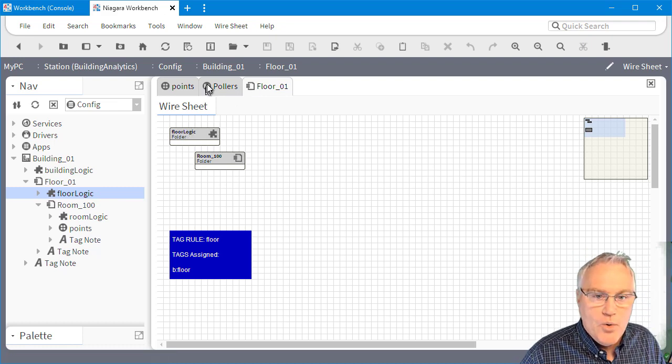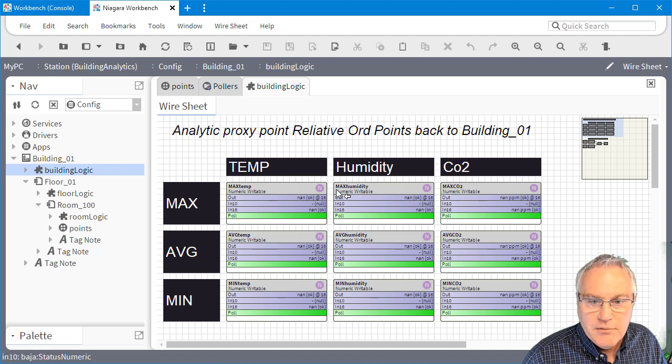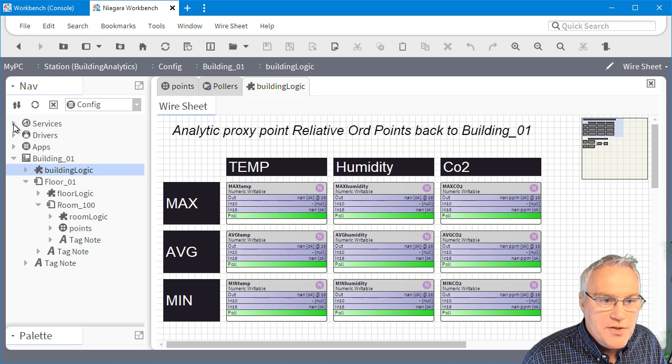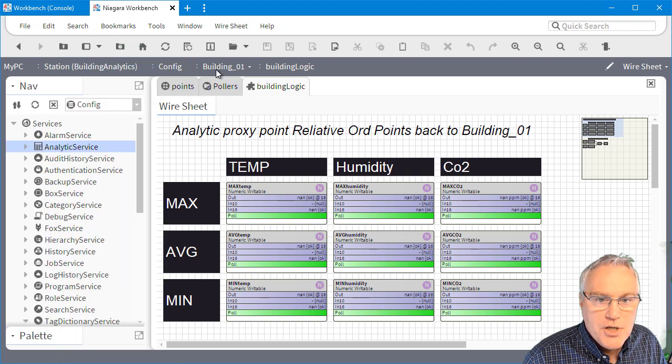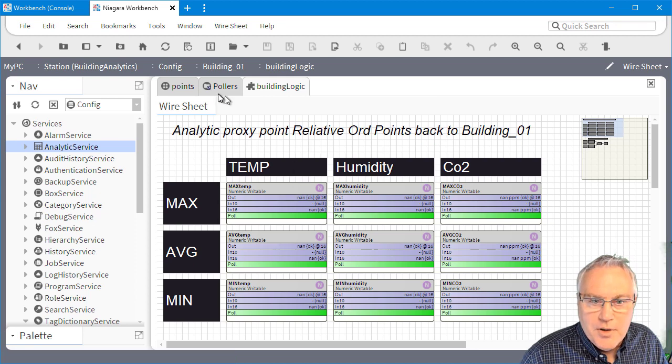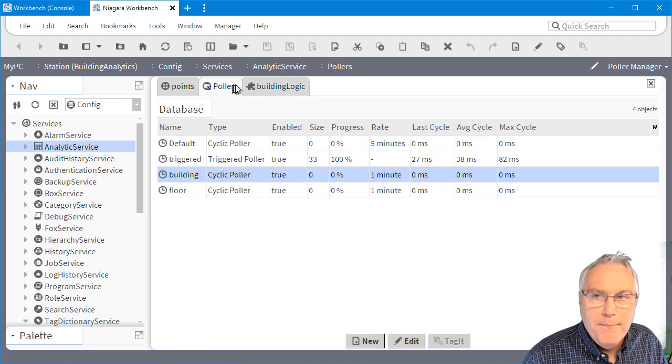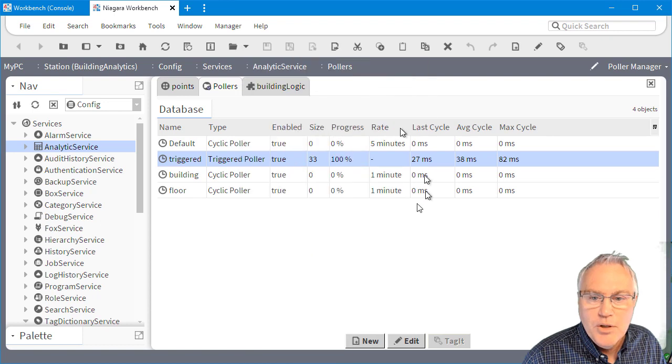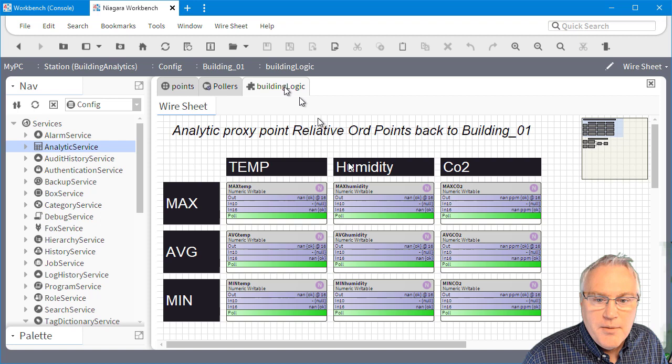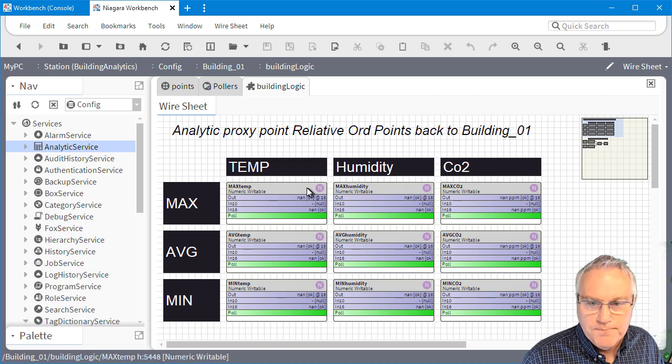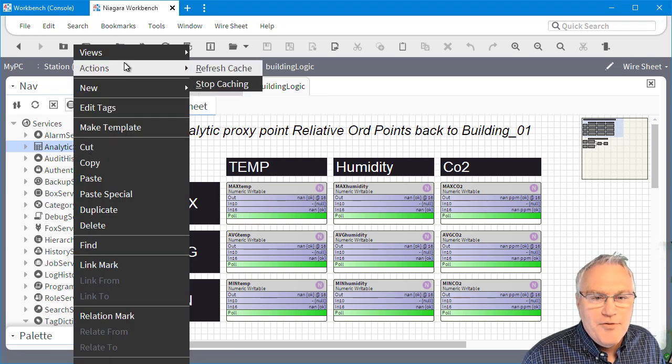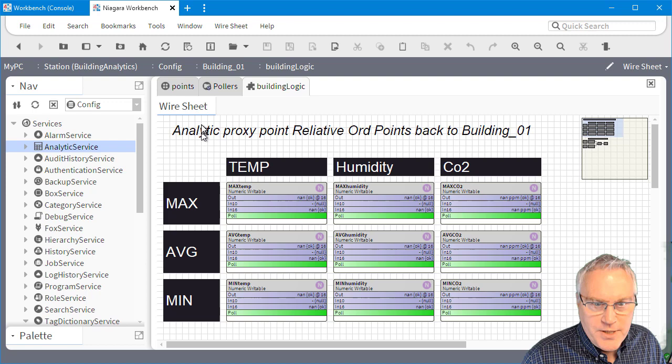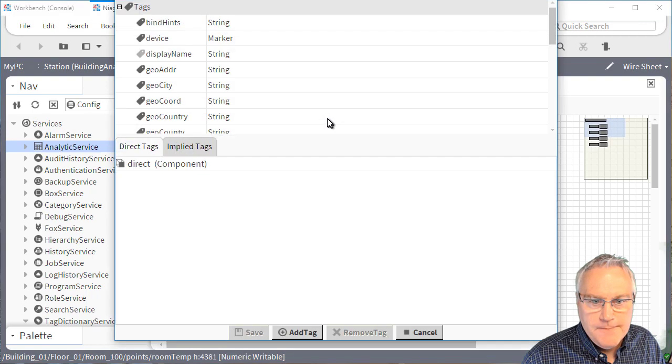So let's go and look at this building logic and let's get some data in there. Usually you'll go into the service. When you add points, you'll refresh the cache and you're off to the races. So what happened? I don't have any data, even though I refreshed the cache because I'm not doing an automatic poller. I have to actually trigger it. So I'm going to go in here and say execute the poller. You'll see that it goes and we get 33 points. Come back and I don't have any information. So first thing I usually do is I refresh the cache, but I know that's not going to work.